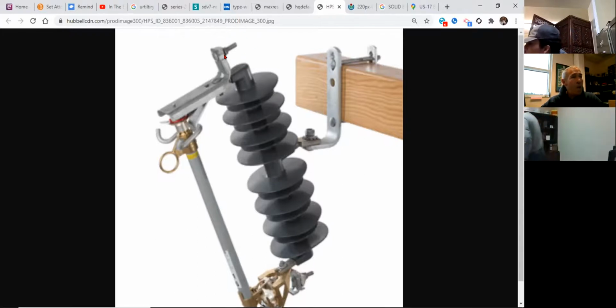As far as a tap line that goes across the highway, depending on what the engineer specifies, we're just going to use a fuse cutout only. It really goes to the point: if I have fused switches and arresters at all my transformer locations, I'm not really worried about the line. I can use a fuse cutout because I'm already protecting at the transformer. Does that make sense?